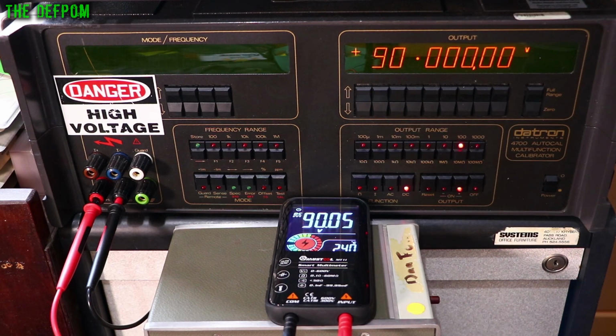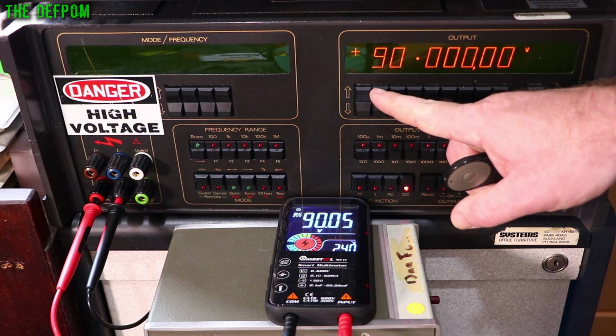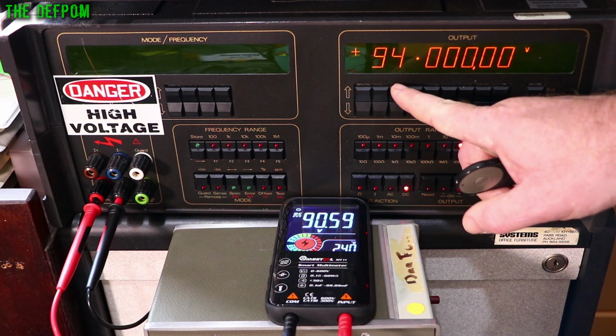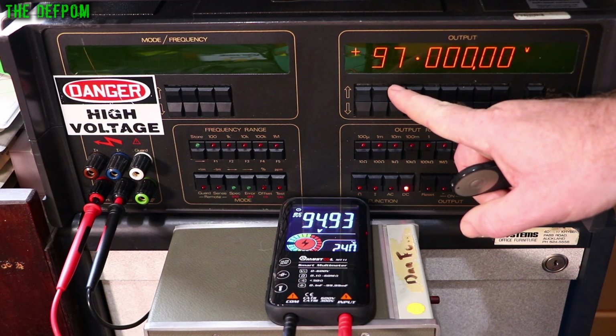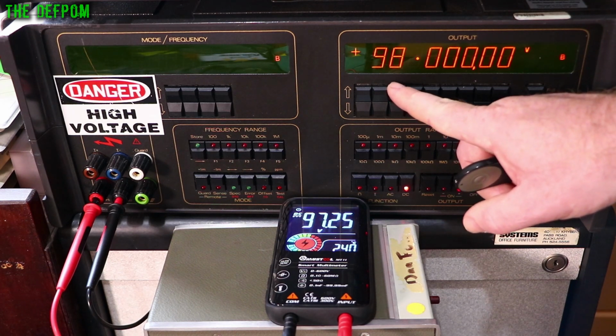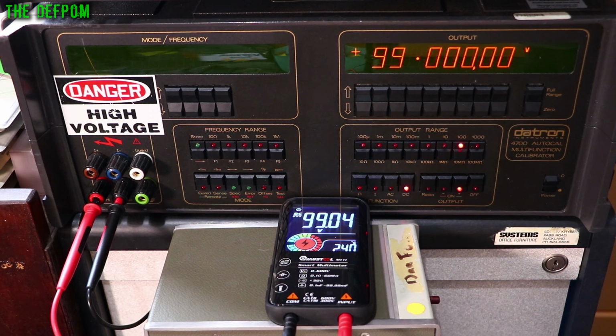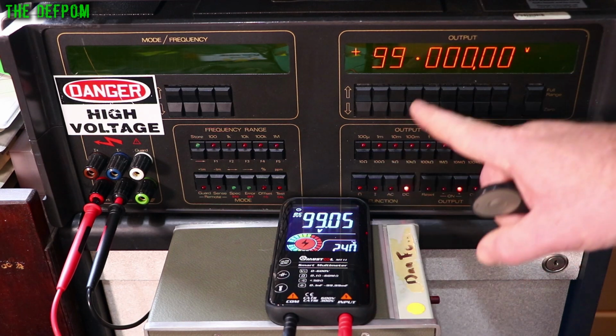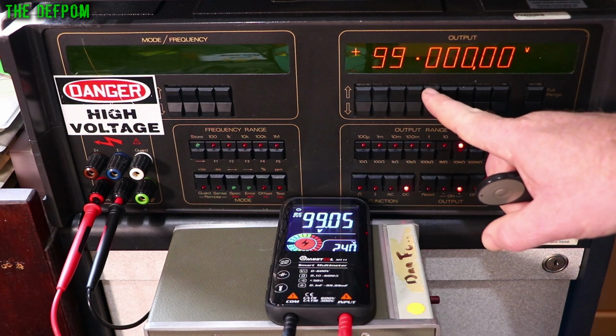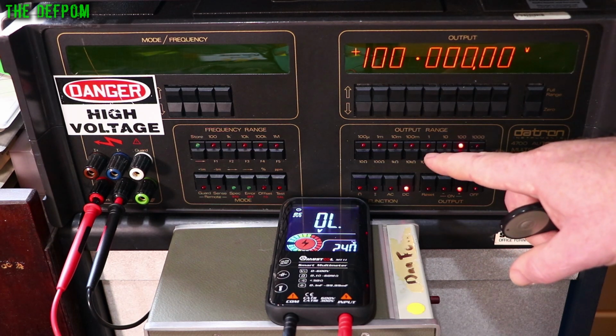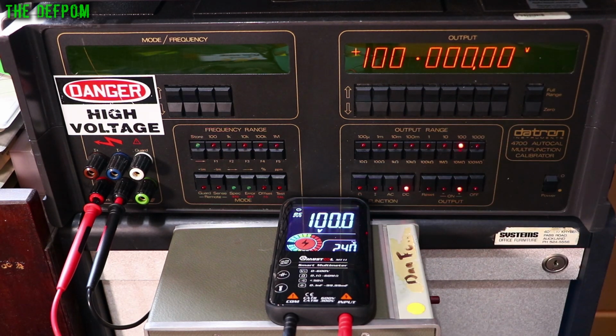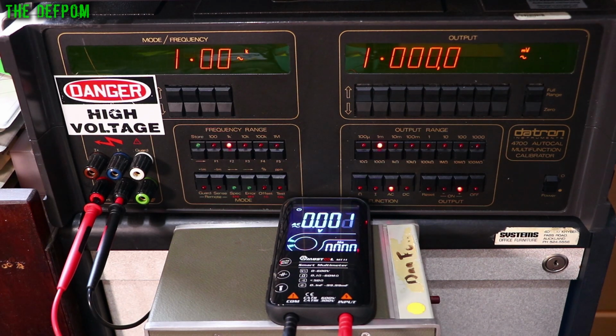Yeah, so my suspicion about calibration points might be correct. See, it's drifting out further and further until it gets to that next range, I reckon. So 99,005. There we go, when it ranged over, it was bang on. So yes, it looks like it's calibrated at the bottom of the ranges, and the upper end is not so accurate. So AC is what I'm on now.